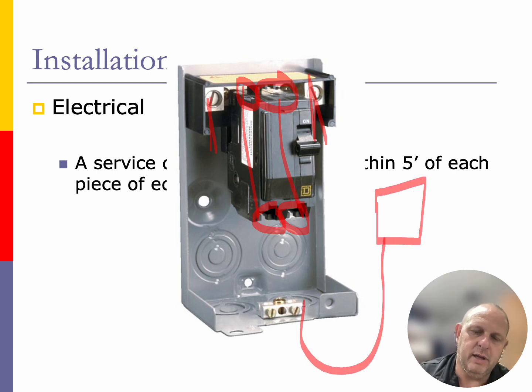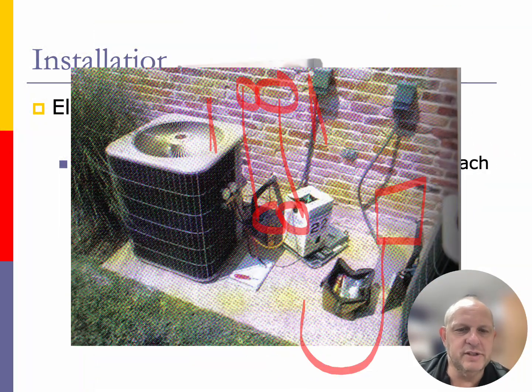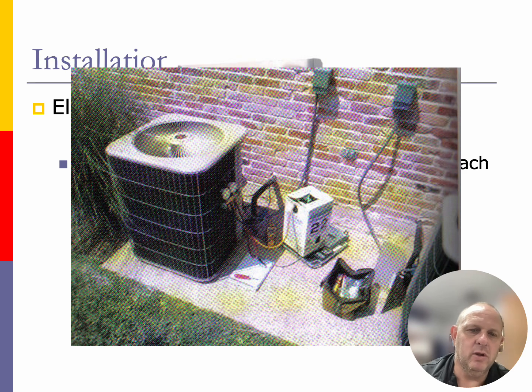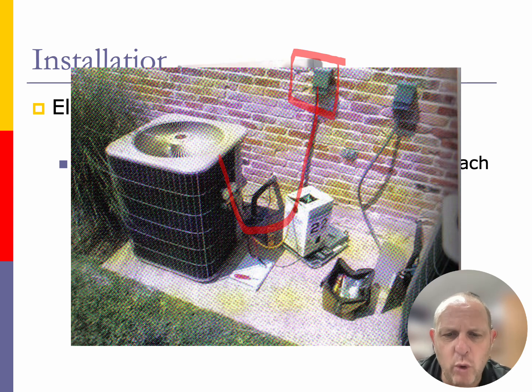Here's an example of the outdoor unit. The disconnect is sitting there on the wall, and then we are going to run liquid tight down and up into the outdoor unit. I always like to run the liquid tight along with the line set. So as I'm coming straight down this wall, I'll come straight down the wall, jump over to the line set as best I can, making it look smooth and nice, and then come into that outdoor unit, strapping it as I go to make it look like a nice and clean installation.